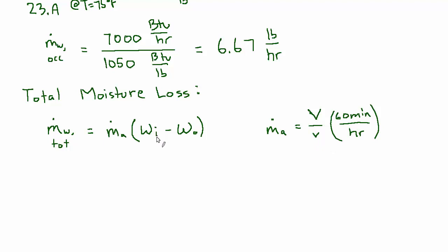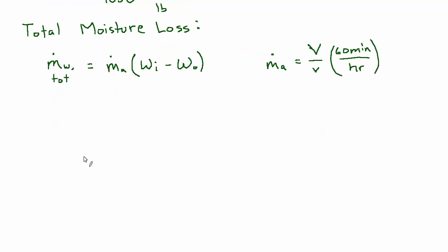So let's look up the humidity ratios and specific volumes for the inside and outside conditions. We'll start with the inside where the temperature is 75 degrees and humidity is 40%. The humidity ratio is 0.00739 pounds of water per pound of dry air. And by the way, when I do these lookups I use a psychrometric calculator so it's very precise. I'm getting a lot of digits here.